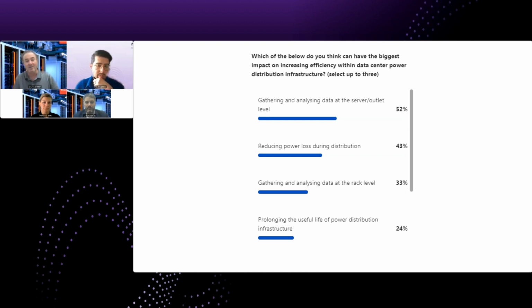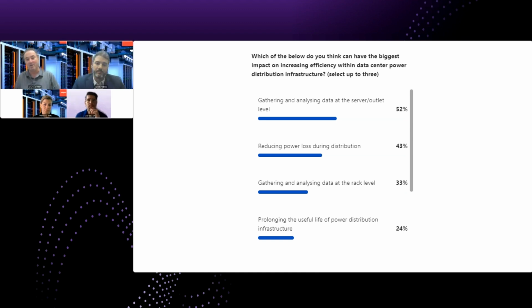There are some gains there, and based on scale, they can be significant - both in how more efficient your server will run, and secondarily in your distribution system, not taking 480 and bringing it all the way down to 120, which is essentially what 208 is, right? It's 120 volts out of phase that gets you your 208. That was talked about a lot years ago, but it's still relevant today - there are efficiency gains in distributing power at higher voltages within your data center.